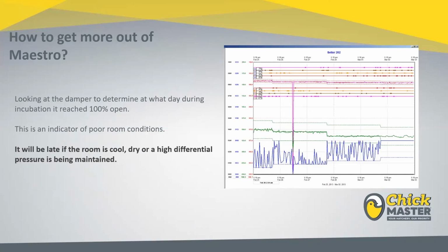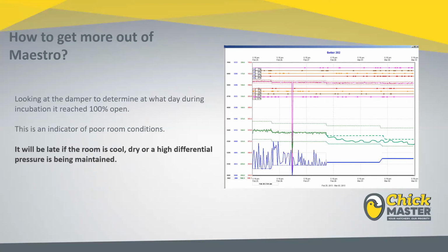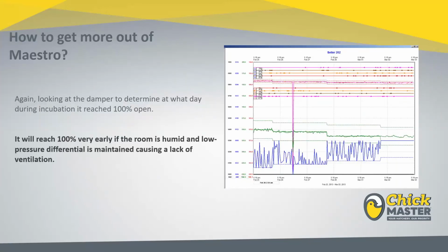And when you see this, oftentimes you'll have a machine that just has a difficult time at maintaining humidity, but the damper itself will follow more of a pattern that's like this, where we're low in our humidity and we're not achieving set point, so our damper will continue a path of just following the minimum damper opening in the stage program. So this is just an indicator that we probably have one of these situations influencing the machine.